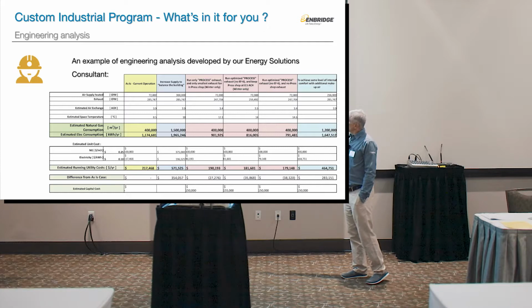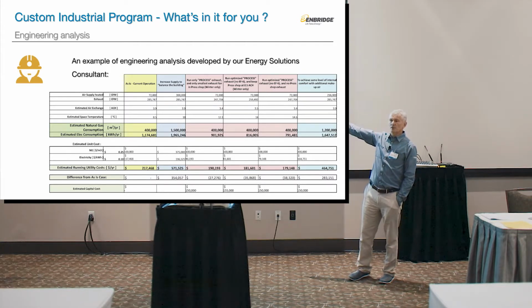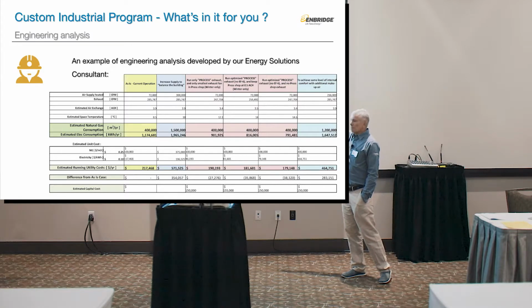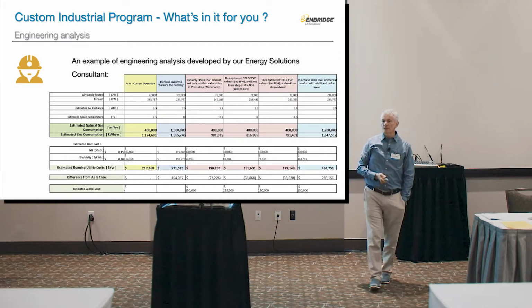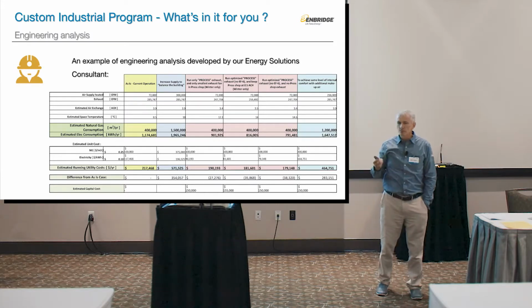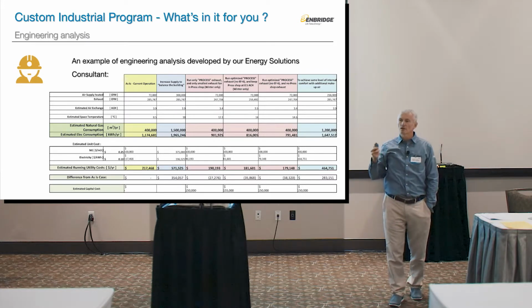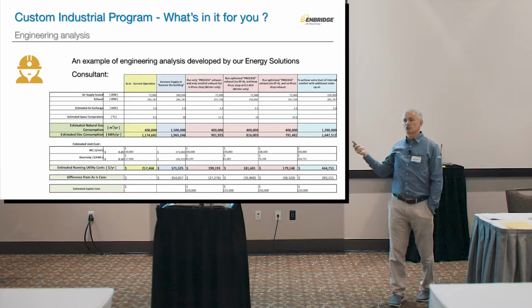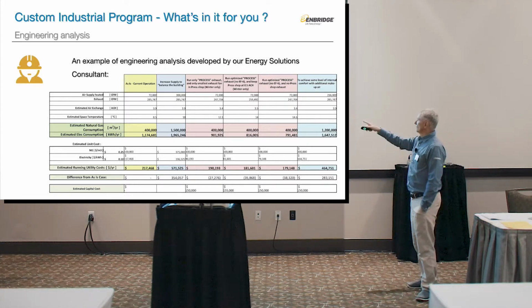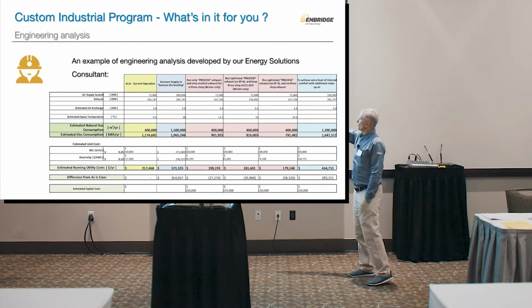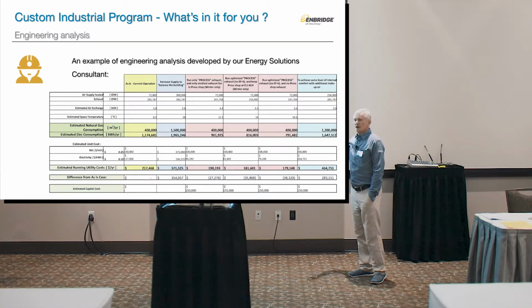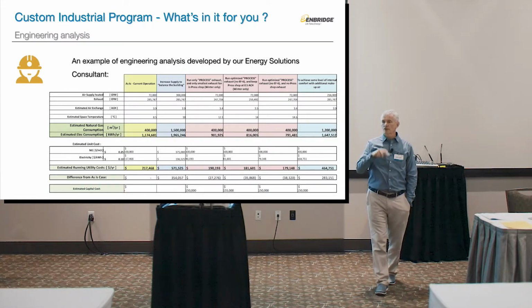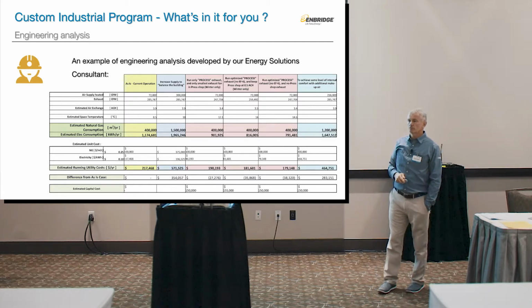Look at their estimated natural gas consumption from the meter, as is, 400,000 cubic meters. If they were to balance the building, they would use 1.5 million cubic meters. You may want to ask yourself, is it worth balancing the building that much to pay that much more? Look at the jump in kilowatt hours per year, from 1.1 million to 1.9 million, just to get that fresh air back into the building.